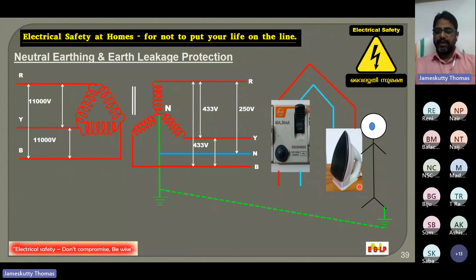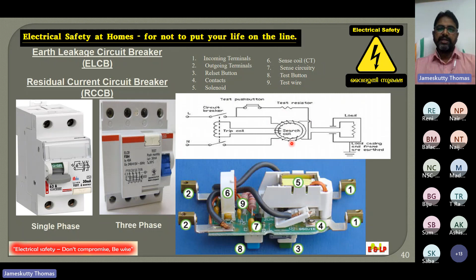It can happen either through improper or loose contact of this neutral earthing, or even because the earthing of our house is not proper. There are various reasons for this neutral earth voltage. And another thing you must note is that if this neutral is loose, your equipment will be getting higher voltage. That is also another disadvantage. If there is higher voltage, suppose say it is 350 or 400 volt, you must complain to KSEB, and it is because of the loose neutral earthing. See here, you can see a coil here, and this coil is checking the currents from the phase and neutral constantly. If there is a difference, this coil will be sensing it, and the circuit will be tripped.